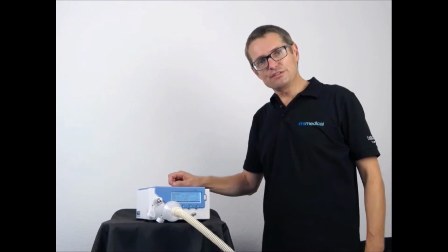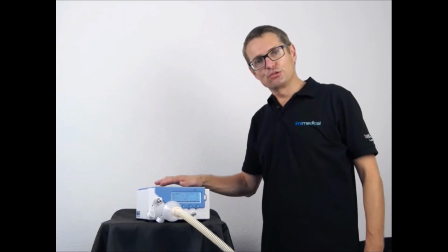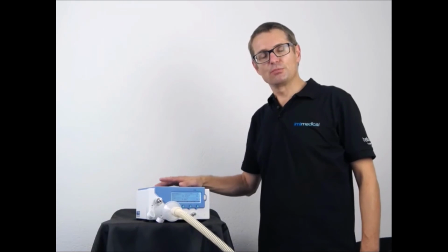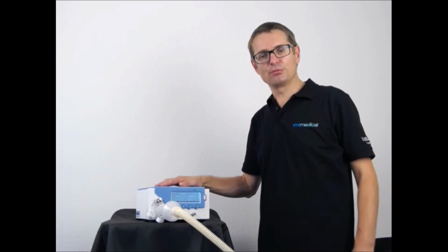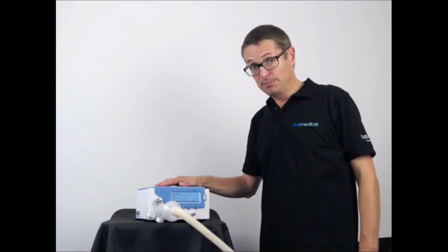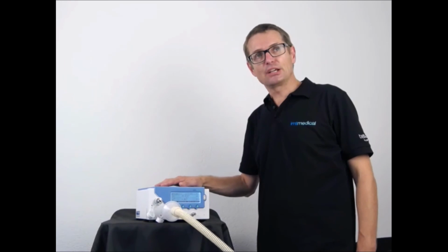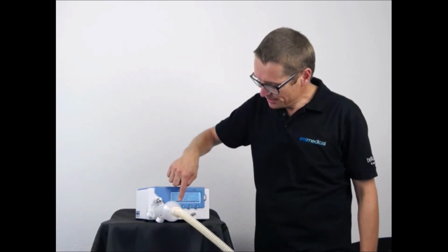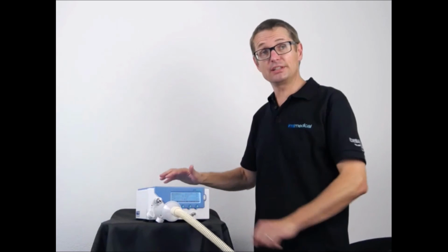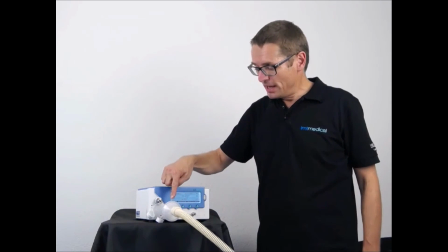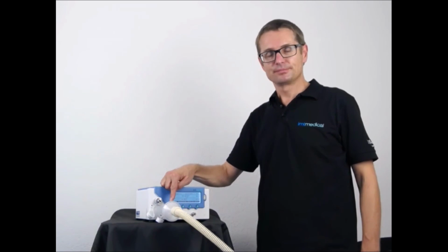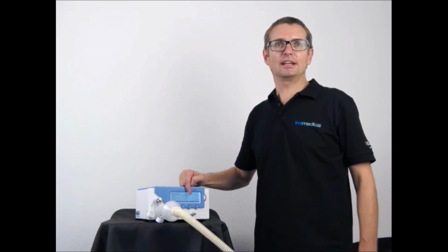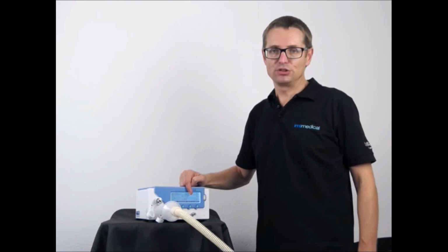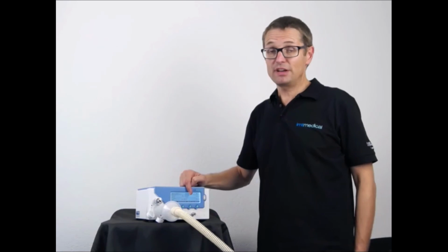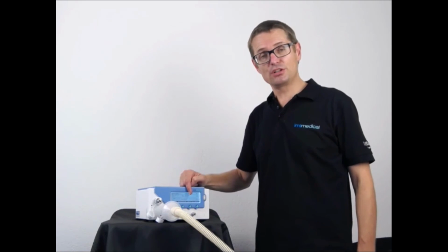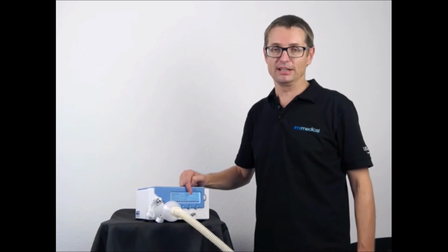So this brings me to an end of this presentation. I would like to repeat the few steps which have to be done before every measurement. One is warm-up, 15 minutes. The second one is zero the device through the menu with nothing attached. Then always use a filter and check the gas standards, gas types, and trigger settings. That's all. That's fairly quickly. Oxygen sensor calibration only has to be done every once in a while.